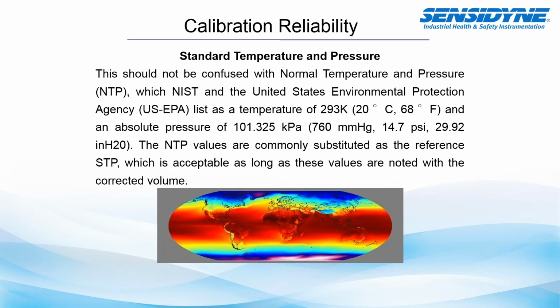Again, you should make sure that you don't confuse this STP with your NTP values. NTP is usually a higher value. The US EPA, for example, lists a temperature of 293 Kelvin, which would be 20 degrees Celsius, and an absolute pressure of 101.325 kPa, which is 760 millimeters of mercury. The NTP values are commonly substituted as the reference STP, which is acceptable as long as these values are noted with the corrected volume. So whenever you're using a corrected temperature and pressure, make sure you actually state what your NTP reference values are.